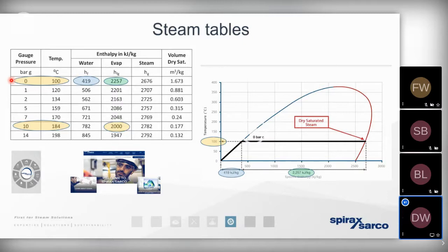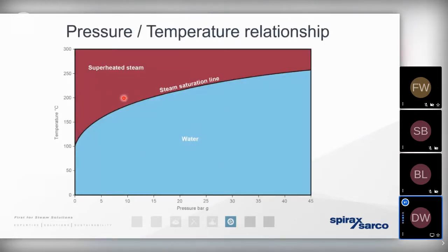So as you can see, if we increase the pressure of the steam, we've reduced the volume. We've increased the total heat in the steam, but there's less useful heat. And that's why in previous weeks we mentioned the benefits of reducing the steam pressure ahead of the process. It means that we're able to utilize that latent heat energy more readily and more efficiently. Now, the other things that the steam tables tell us that we've discussed in previous weeks, it's that pressure to temperature relationship. If we know the pressure of the steam, we know the boiling point of the water, and therefore we know the temperature of the steam. For example, if we're generating steam at 10 bar gauge, the boiling point of the water would be 184 degrees, and therefore the temperature of the steam is 184 degrees.